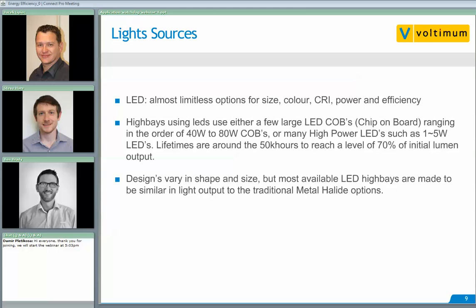LED is the next light source. LED has almost limitless options for size, color, CRI, power and efficiency. For high bays using LEDs, there are large LEDs ranging from about 40 watts to 80 watts, known as COBs (chip on board), or you can use many high power LEDs such as 1 to 5 watt LEDs. Lifetimes are around the 50,000 hour mark to reach a level of 70% of initial lumen output — known as L70.